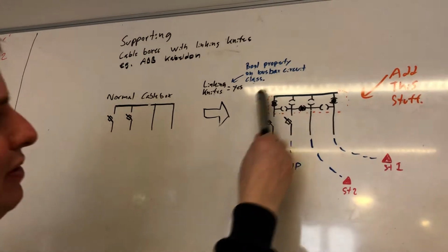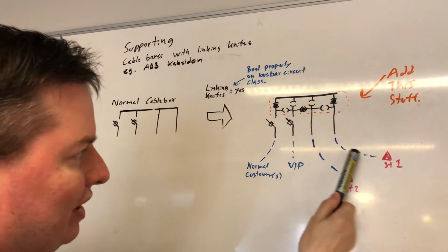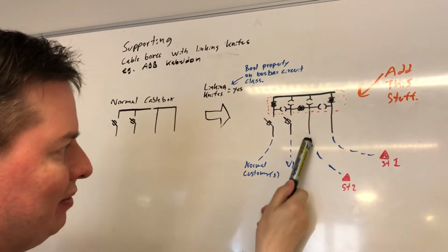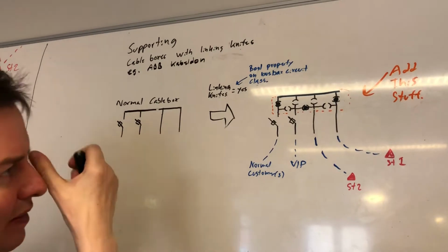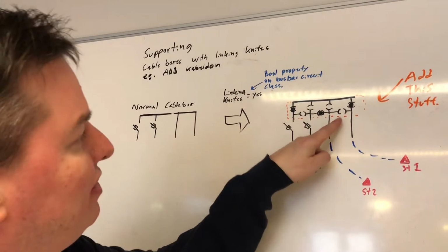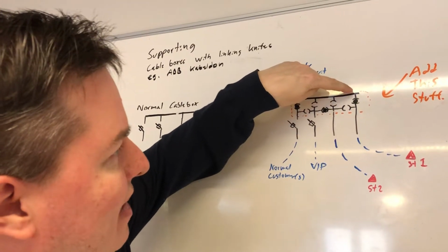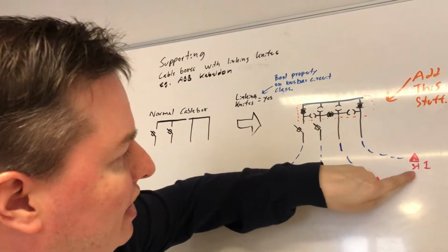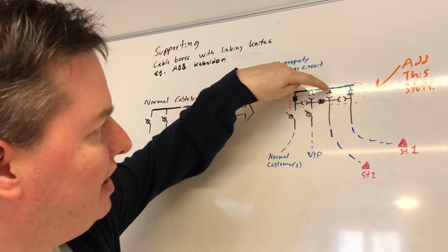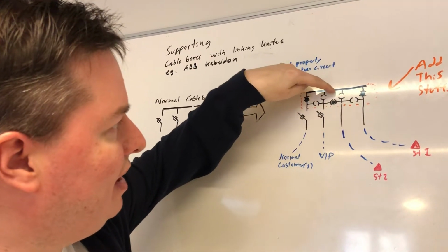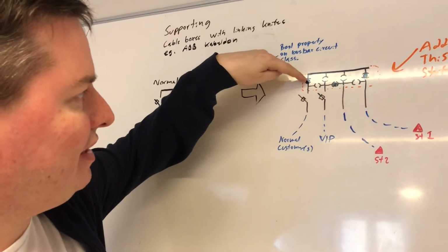So if this cabinet here is fed from station 1 and station 2, there goes a cable inside this bay and a cable inside this bay. So it's actually fed from 2 different places, right? Then you might have a situation like this, where they have connected this bay to the bus bar, right? So station 1 is feeding the bus bar, and you can see the power runs here, cannot go down here, it's disconnected. It cannot go down there. And here's the connection, and it will go down.